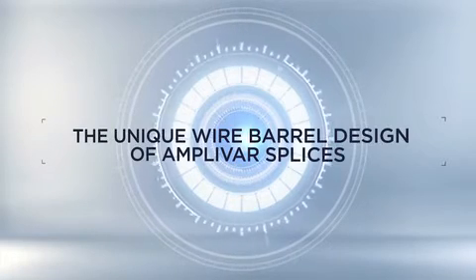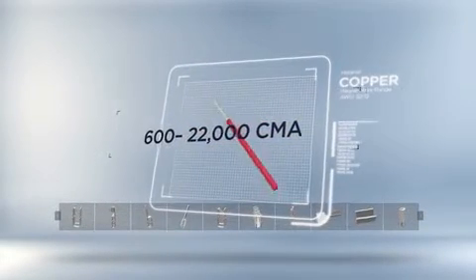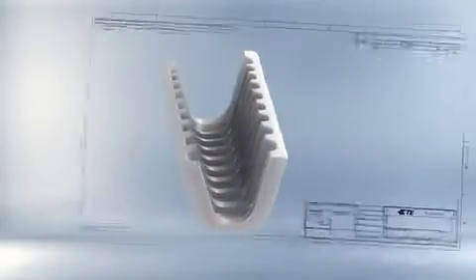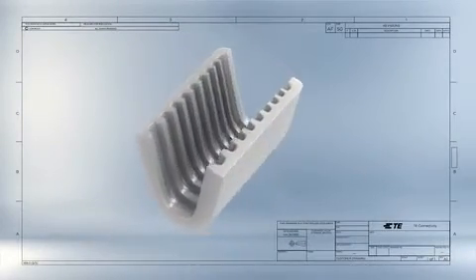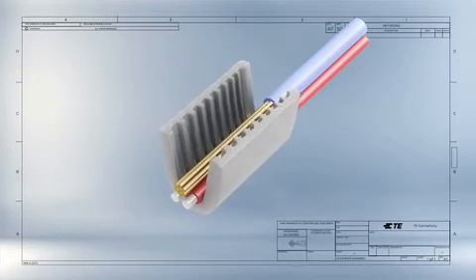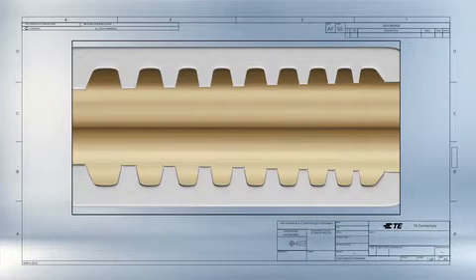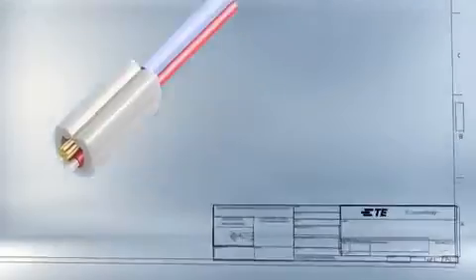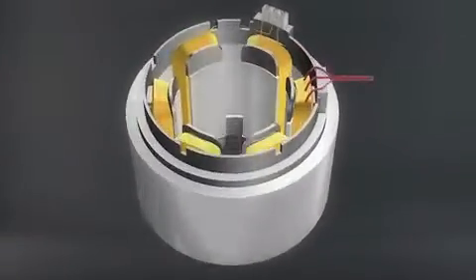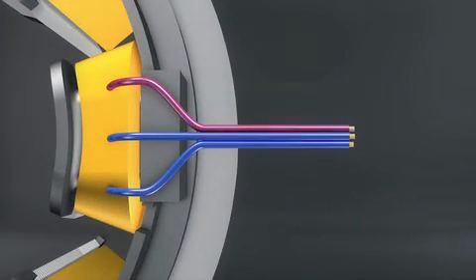Amplivar terminals and splices are crimp connection technology products that can be used for 600 to 22,000 CMA magnet wires. Amplivar products have specially designed and processed serrations with sharp burrs which pierce the insulating film of the magnet wire and increase the contact area during the precisely controlled crimp. This creates a high tensile strength, gas-tight electrical connection that is corrosion resistant. One Amplivar splice can crimp a maximum of three magnet wires of copper, aluminum, or a combination of both.